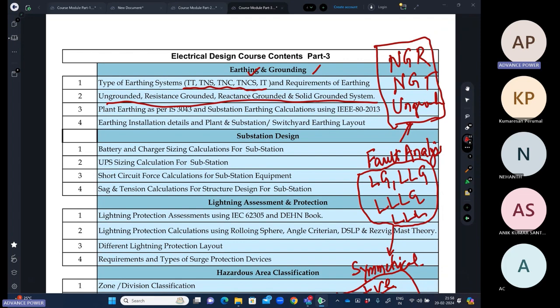We will do the earthing calculation as per IS 3043 for the plant substation, and we'll use IEEE 80. In IEEE 80, when we study, everything is related to earthing. With the earthing system, we will be able to calculate the fault current that will come when there is an LG fault or an LLG fault.